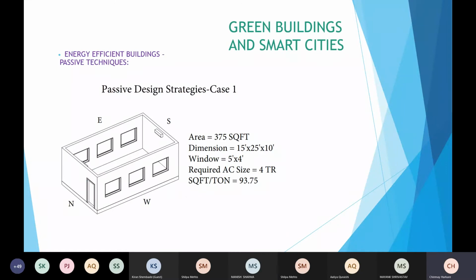To give you an idea, this is a simple 15 by 25 feet room which we designed yesterday, and we are calculating the size of air conditioning required for this typical building with three windows on one wall, total six windows. It is 10 feet high, 15 by 25, 375 square feet space. This can be anything - a school classroom, a hotel room, or an office space.